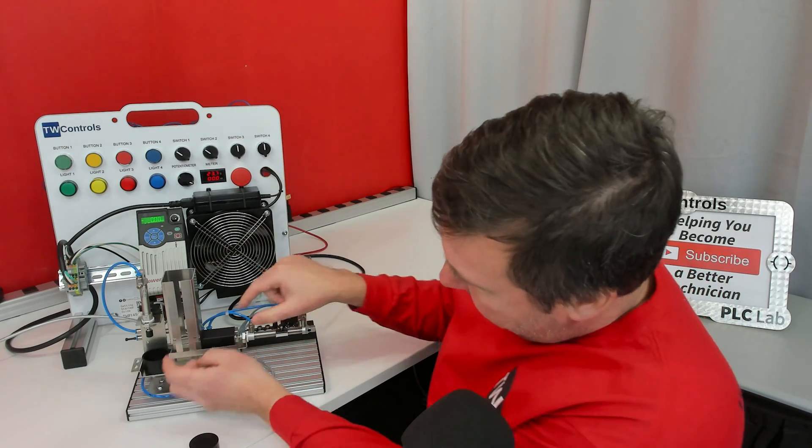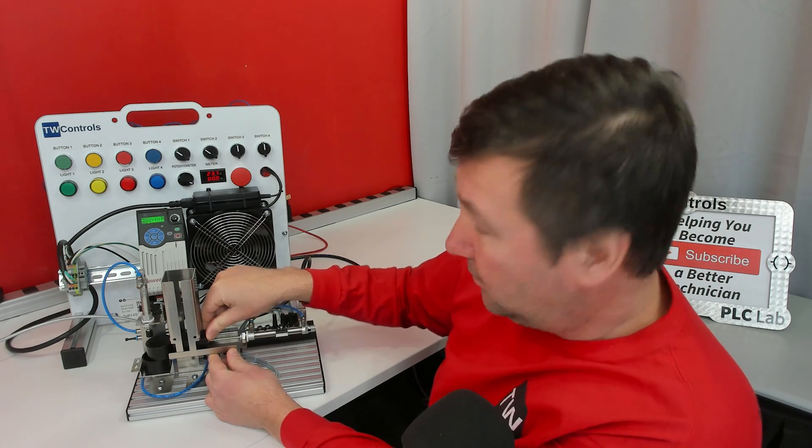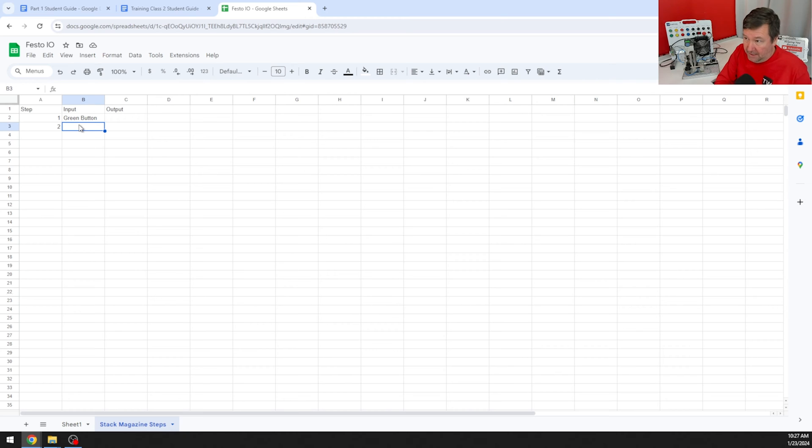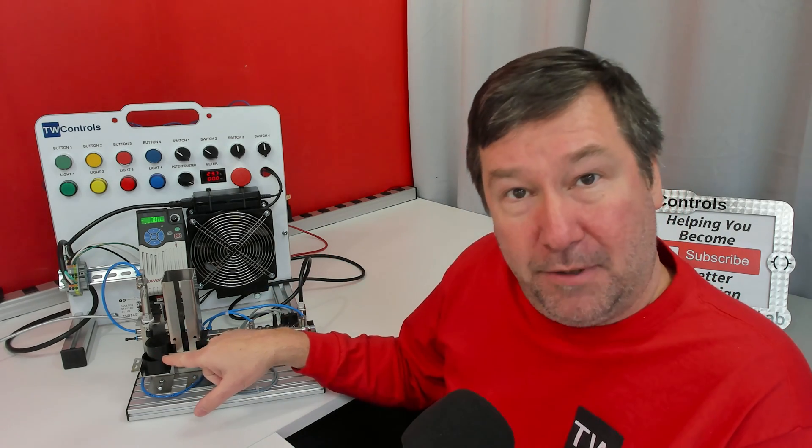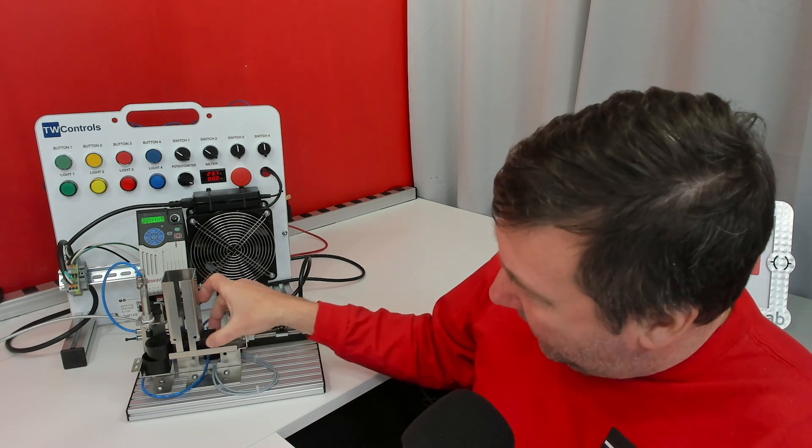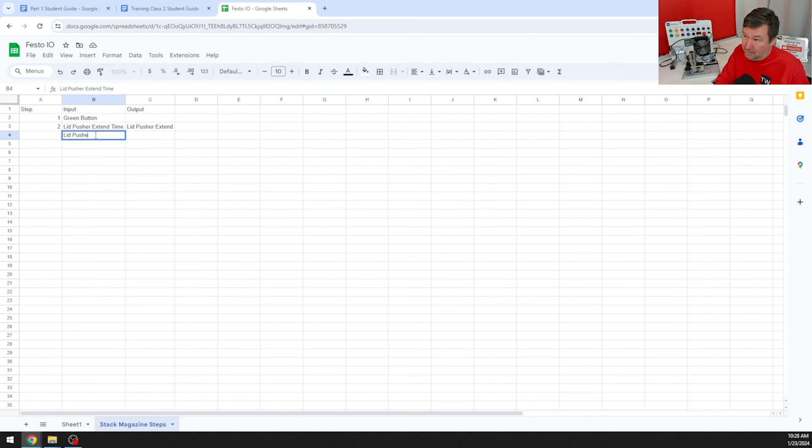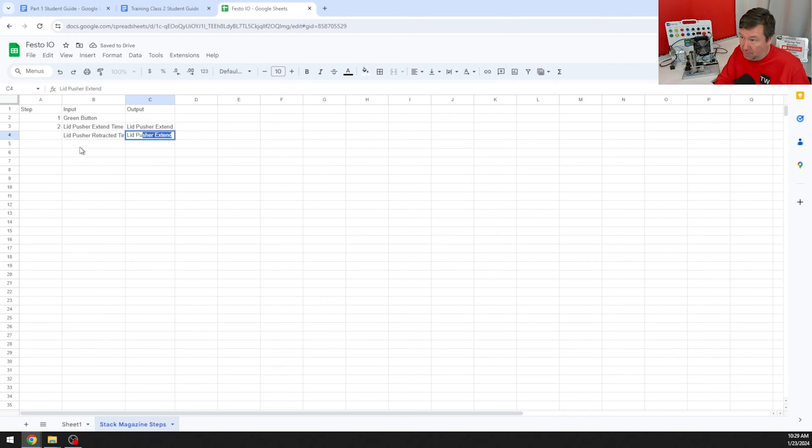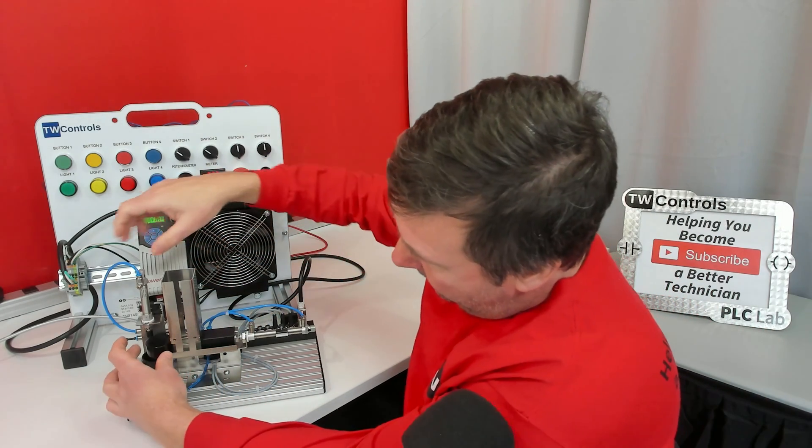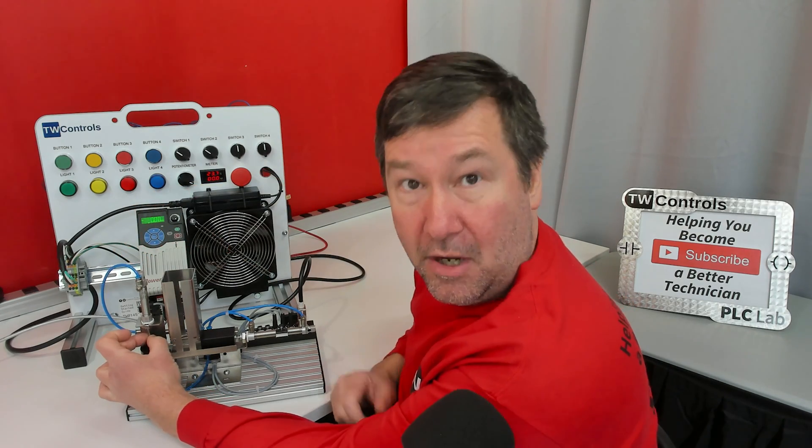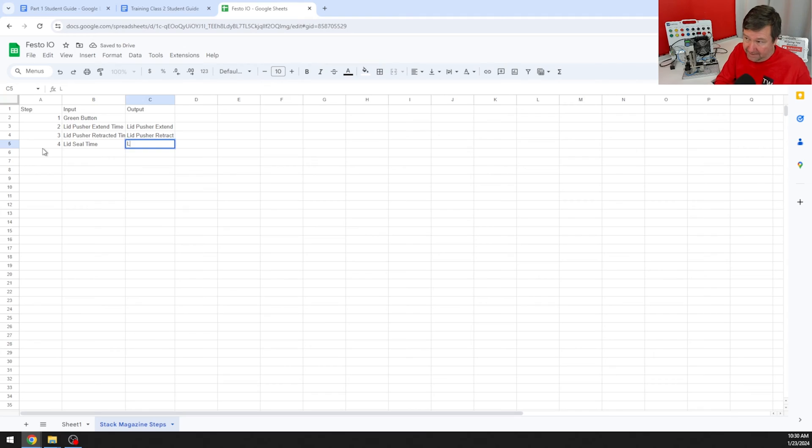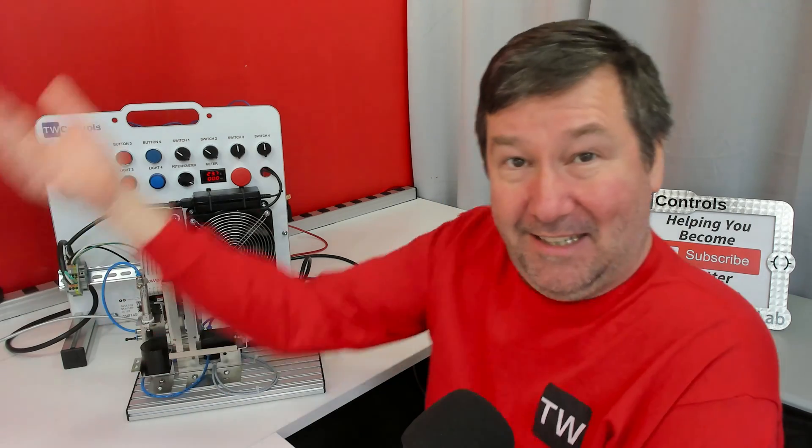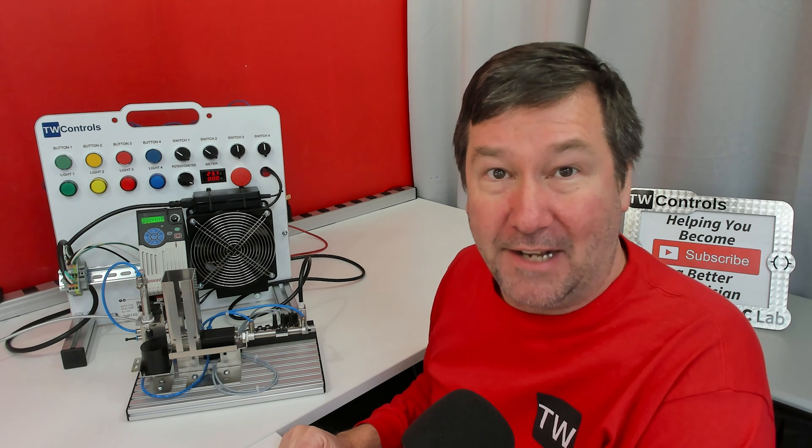On step two, that's going to be extending the cylinder out. We're going to use a time to know that we have extended it out. So step two's input will be lid pusher extend time, and our output will be lid pusher extend. After it is extended and put the lid in place, next we need to retract the lid pusher. Our input will be lid pusher retracted time, and our output will be lid pusher retract.